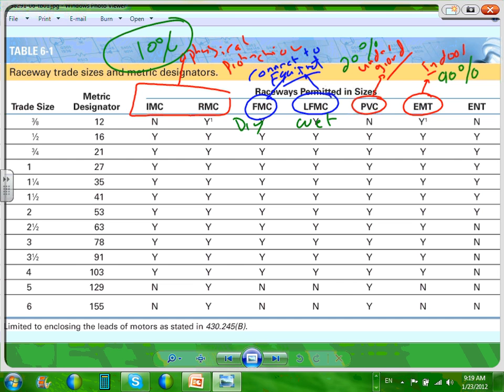Take the same rooftop unit, and let's say I have a fan, an indoor fan, right here, and I'm going to tie it to the fan because the fan vibrates. I don't want to tie it with EMT. Would I be able to tie it with an EMT? It's not a good idea to tie to it with an EMT because of vibrations. The whole EMT system will be vibrating. So what would be my conduit of choice for this indoor piece of equipment? Flexible metallic conduit. Can I get you guys to understand the difference between all these different ones that we highlighted?